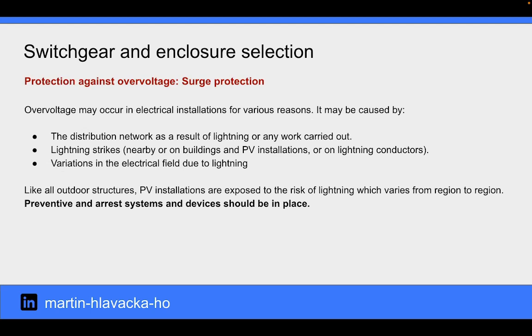Overvoltage may occur in electrical installations for various reasons. It may be caused by the distribution network as a result of lightning or any work carried out, lightning strikes, or variations in the electrical field due to lightning. Like all outdoor structures, PV installations are exposed to the risk of lightning, which varies from region to region. Preventive and arrest systems and devices should be in place.